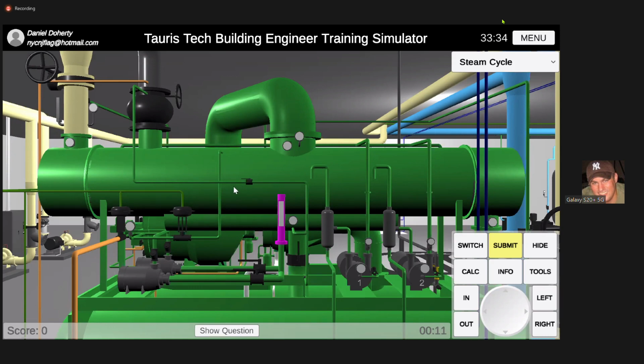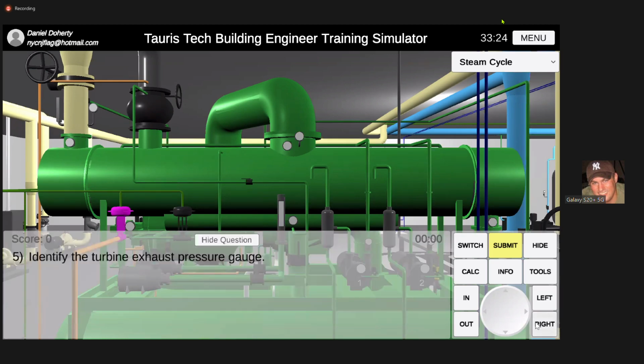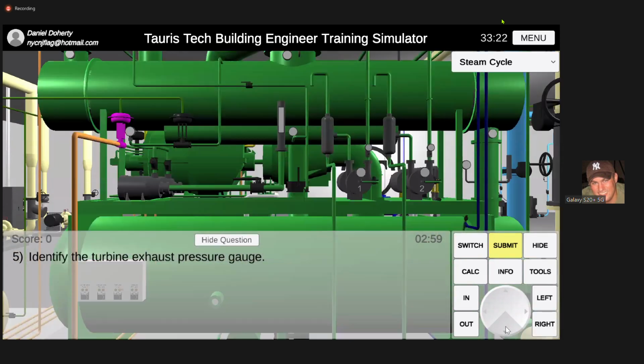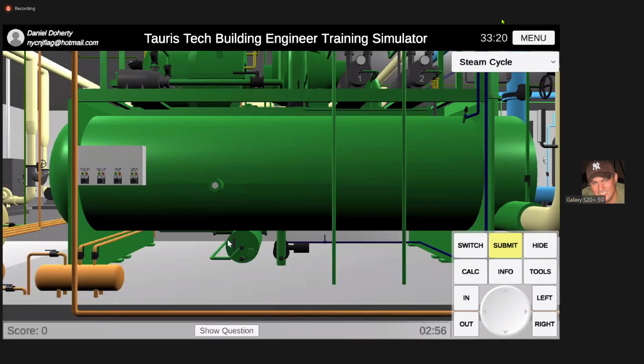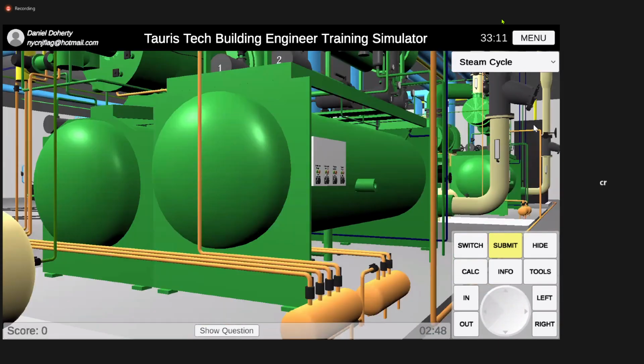When you have a high float, that means there's too much water in the surface condenser in the hot well. This valve closes, and the overboard valve opens, and it dumps the excess down a drain. We don't have a drain here, but this goes back to the boiler, and that's used as makeup water for the boiler. We actually have a boiler in this room. See the black back there?